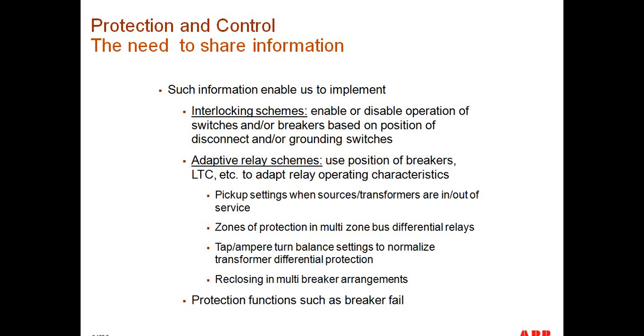Another case is adaptive relaying schemes: the use of position of breakers and load tap changers to adapt relay operating characteristics. What we mean by this, in the case of position of breakers, is if you have a bus that's fed by two transformers and, because of certain conditions, one of the transformers is taken offline, that could considerably change the available fault current, for either ground faults or phase-to-phase faults. In certain circumstances, that may merit the change or adaptation of the settings of some relays inside of the substation. So that information, that position or the topology of the substation, is important to know to be able to make that decision.